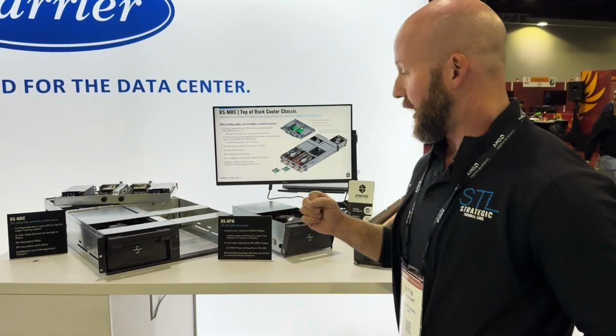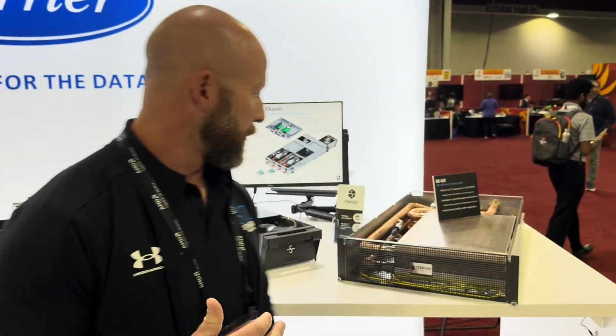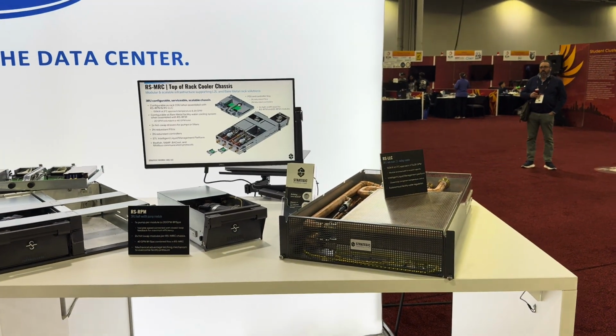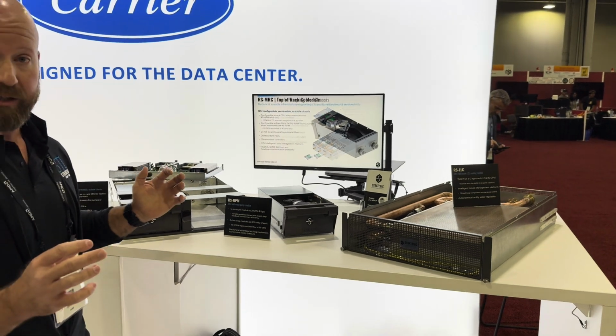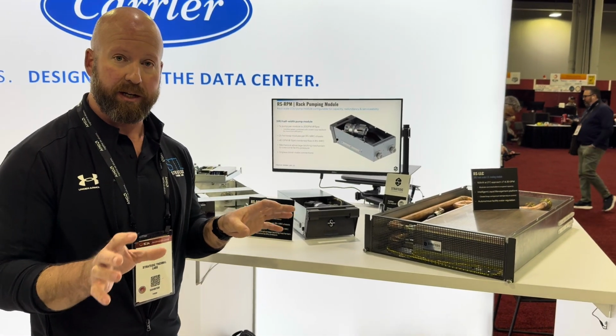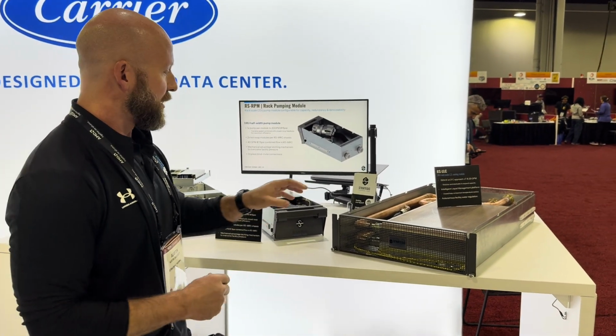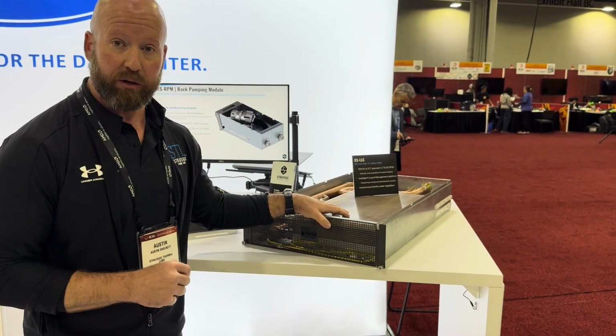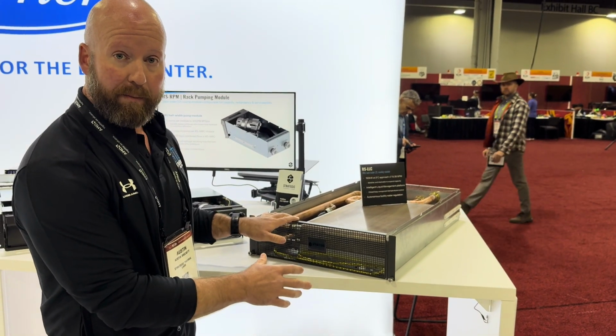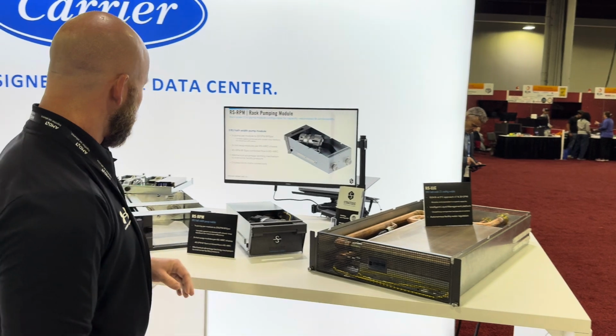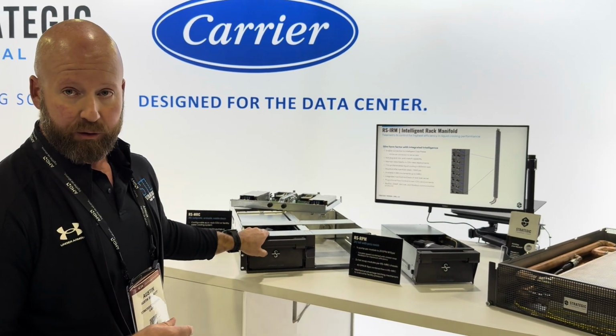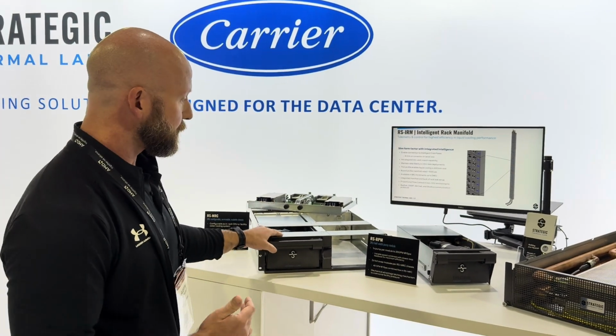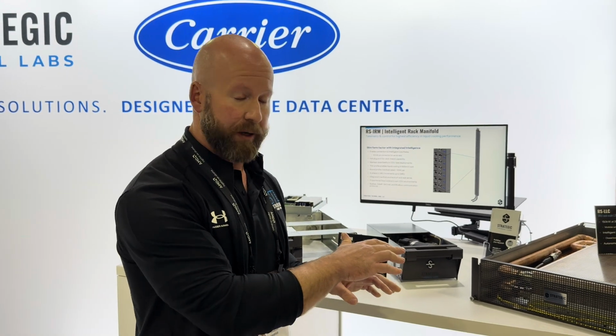Next up is the STL CDU solution. So basically, we took the components of the coolant distribution unit that you normally see in a data center, and we discretized them into 2 different functional blocks. On the right side is the brazed plate heat exchanger. This is a 3U rack mount box that'll fit into a 19-inch rack. On the left side, we have our pump module. This is a 3U box as well. Together, these are a 6U combination.